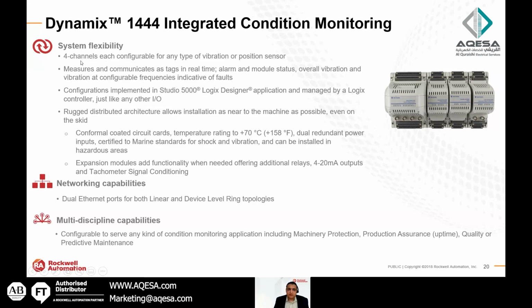So this module comes with 4 channels to be configured for any type of vibration or position sensor. If you have an accelerometer, velocity meter, proximity sensor, any of them can be connected to any of the 4 channels of this guy. Measurement, communication, tags, alarms, everything will go over Ethernet to the Logix CPU. And that's what makes it special.